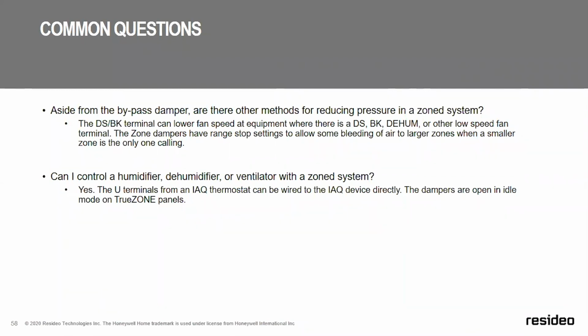Doing this allows you to have one point of control for the IAQ equipment, and typically those are set up so that you set them to maintain a certain humidity level, and then you just forget them and they run. The process of humidifying or dehumidifying the house will naturally cover the whole house. The exception would be exceptionally large houses. In those situations, we do have other ways of controlling multiple units throughout a house, but those are kind of specialized. So again, I'd refer you to your contractor development specialist. They are happy to help you design a system.